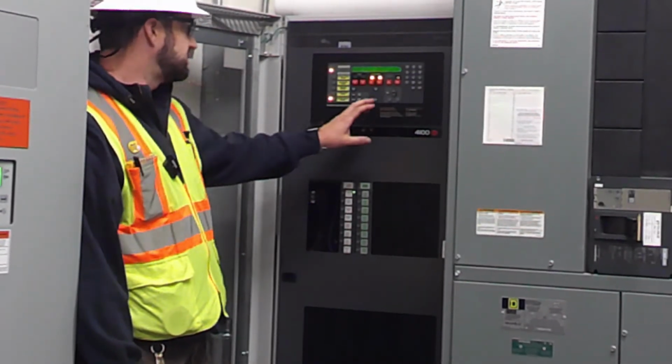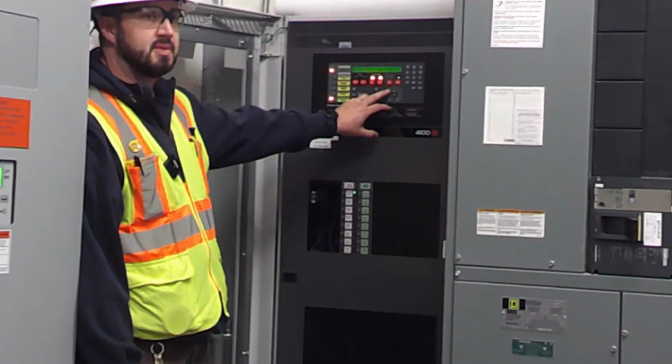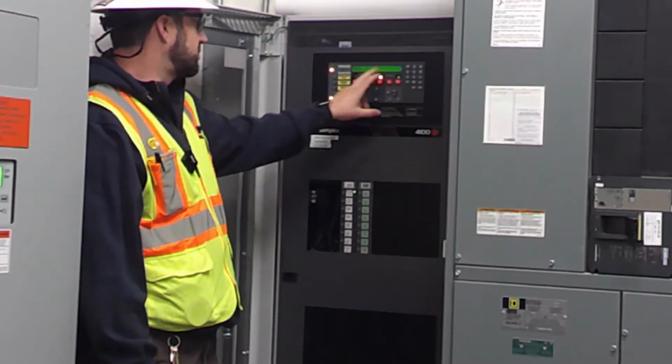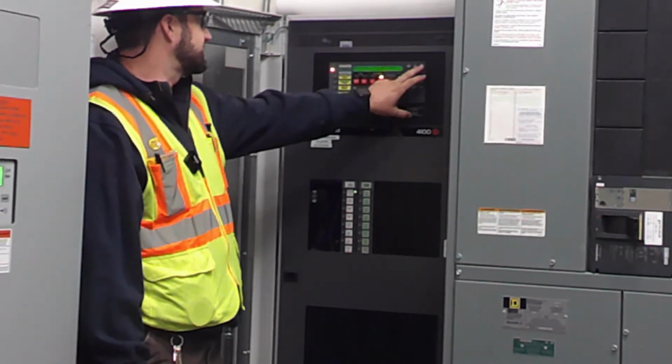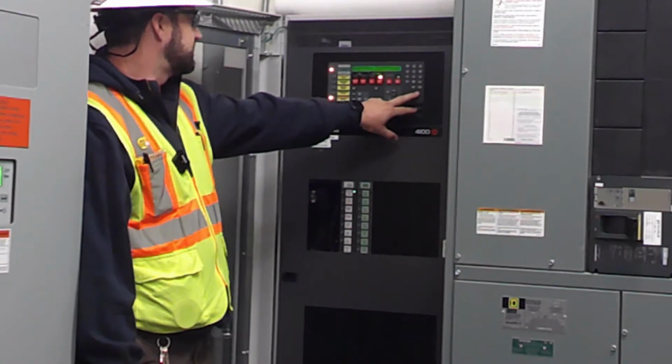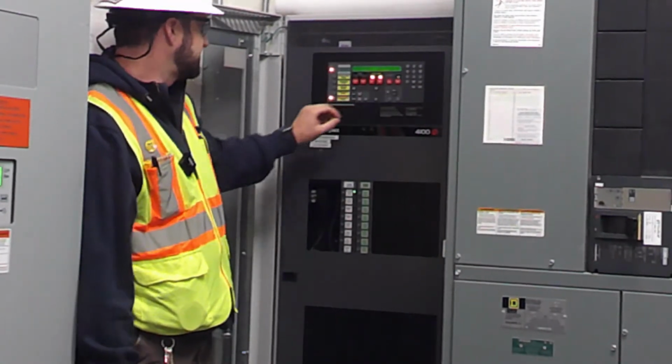Anything else on the panel? Do you know how to log into them? 323. Yep. Menu, change access level, enter 1 for login, enter passcode 333. You are now logged in. You hit clear a couple times, it'll back you out to the main menu.